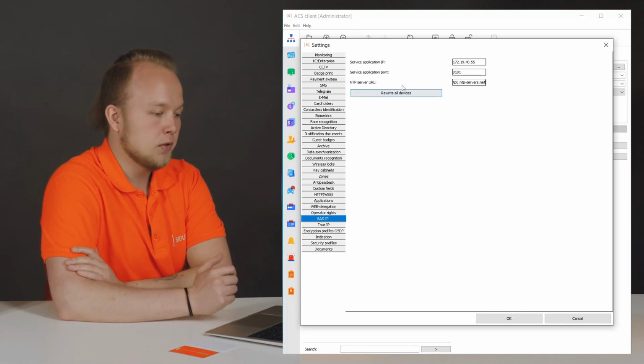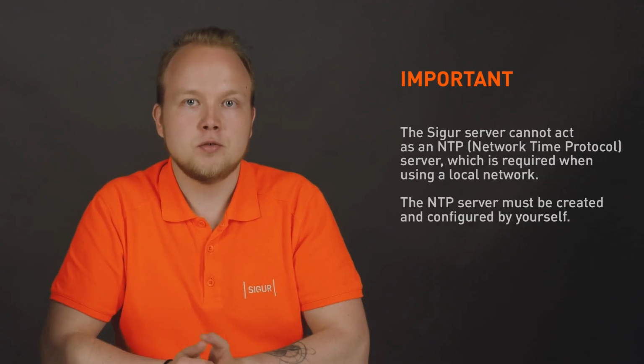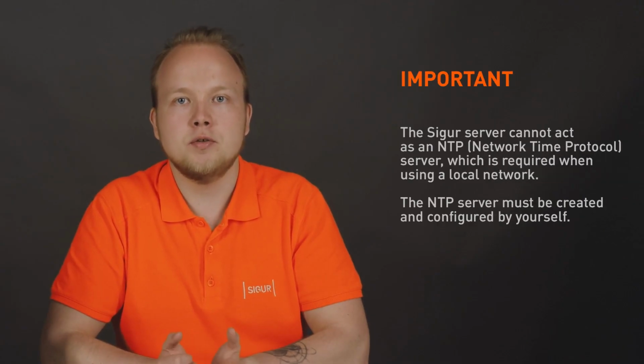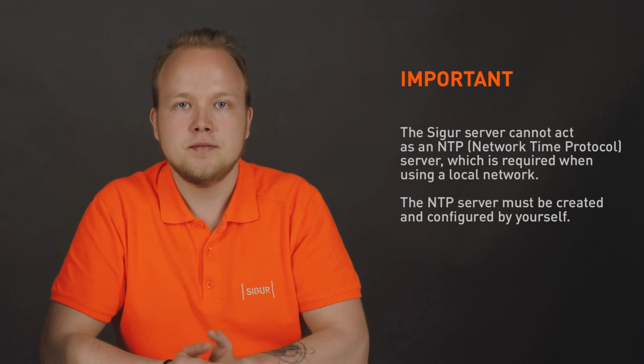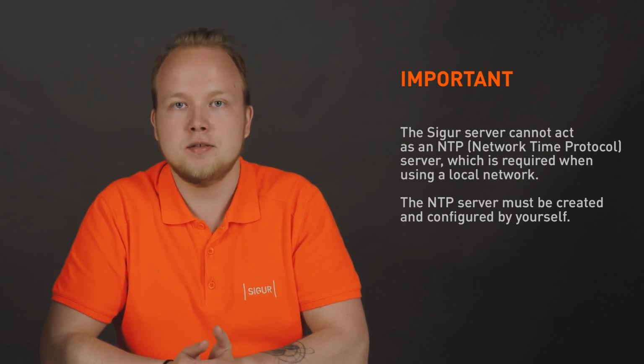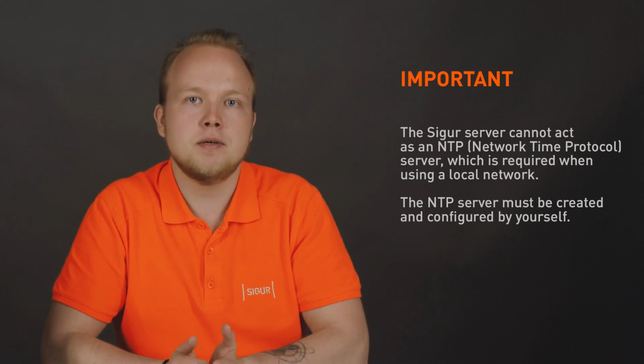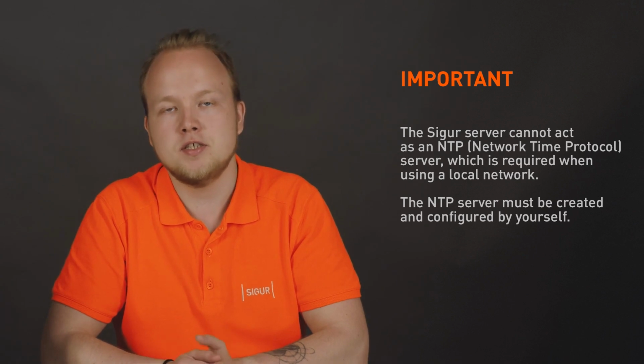Here you will also find the Rewrite Device Memory button, which allows you to forcibly rewrite all data in the memory of the connected intercom panels. It is important to note that if you are using a local network, you need to create the NTP server yourself. The Sigur server cannot act as an NTP server. If an NTP server is not specified, it may eventually lead to incorrect integration operation.